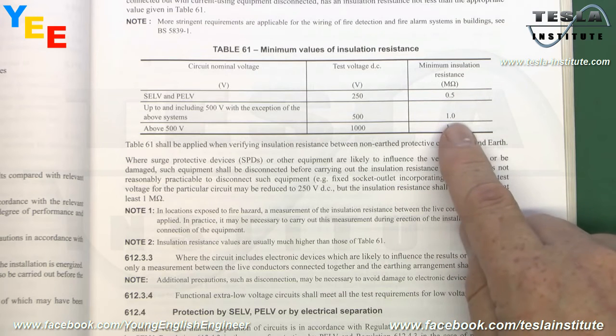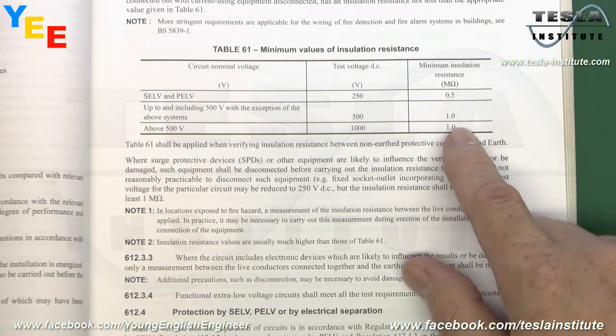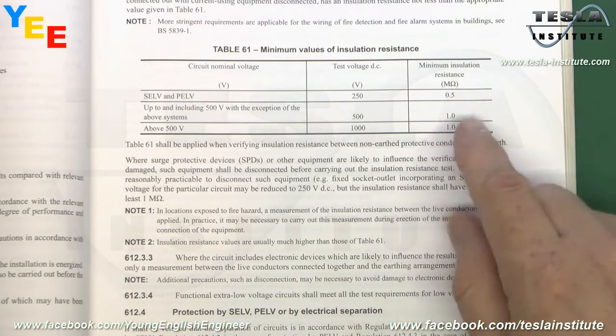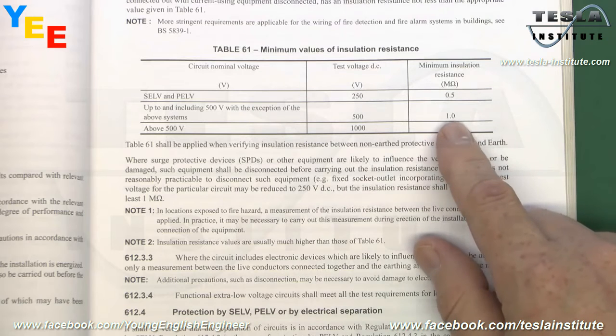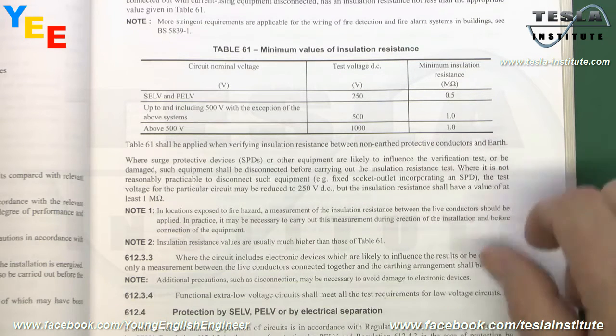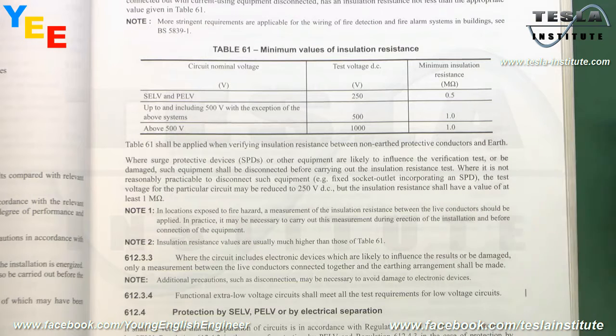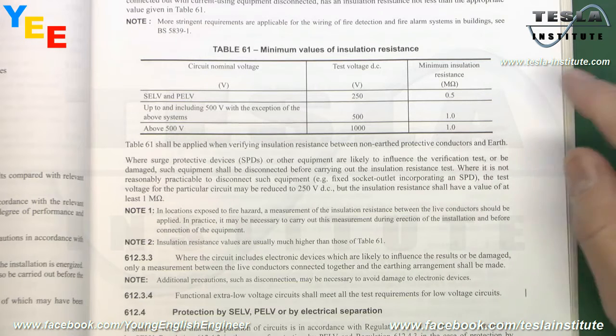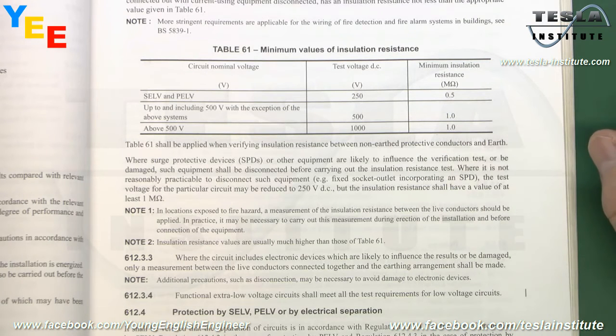Certainly anything in the region of 1 would be worthy of further investigation. And even on an old installation, if you found something around the regions of 1 or 2, again, it's something you definitely want to investigate and find out why it's actually so low, because although theoretically acceptable, in the real world you would want it to be considerably higher than that.